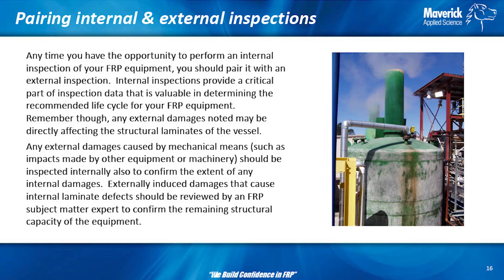Pairing an internal and external inspection is our preferred method. What we like to do is understand what's happening outside from what's inside the vessel. The best way to inspect internally is visually. We've worked with drones, bore scopes, and we can also take UT measurements on the outside and tell you how thick it is. But the tank shell doesn't normally fail — your welds fail, your bottom comes off, or a flange leaks. You can't really tell until you're inside looking to see if the bottom knuckle is damaged or if internal laminates are getting washed off.